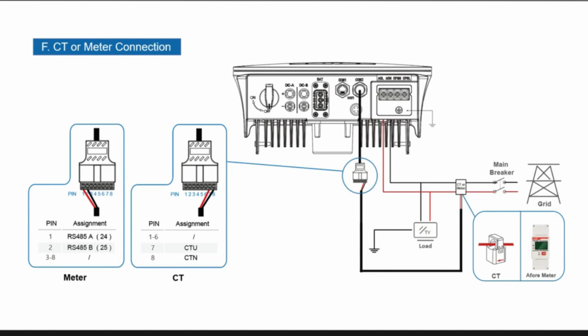Because you've got a master and a slave inverter, the surplus from the inverter without the battery would mean there was more energy left from the one with the battery to actually charge the batteries. And if it sees it exporting out, it's going to charge the batteries at its maximum rate. So then it would use it on both sides. Yeah, indirectly, yes. I would connect both of them together, right? Yes. Any other questions? On the single phase first? We can, is it 6? We can connect up to 6.